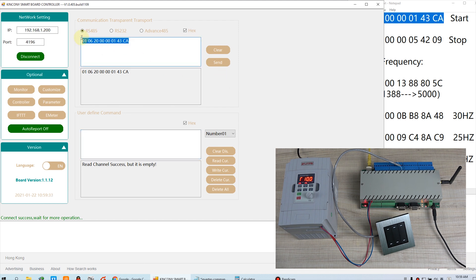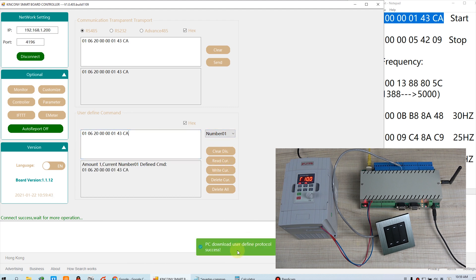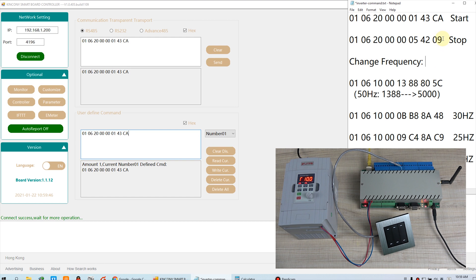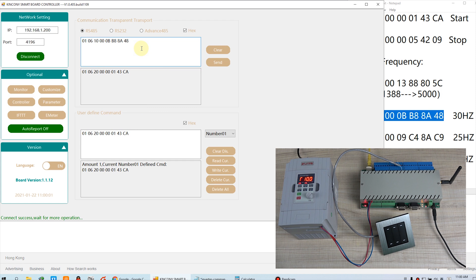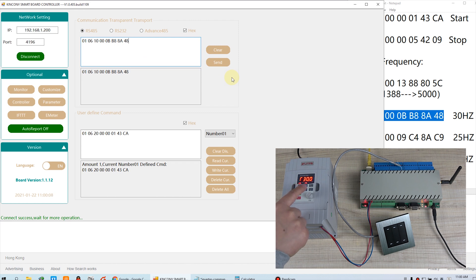So we can copy this start command to this window, and this is define command number one. We can press write. Okay, write successfully. Now we can choose the next one. We can test our frequency command — so we can copy and paste to this window and press send. Okay, you can see the inverter has changed to 30Hz. It's right.